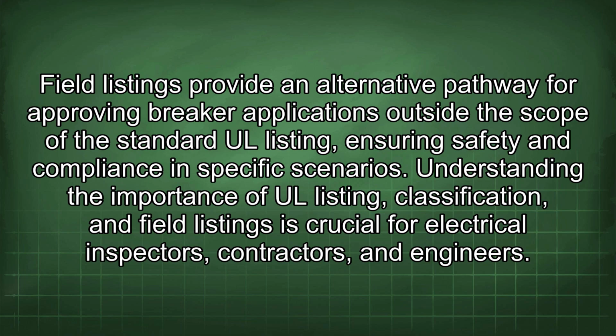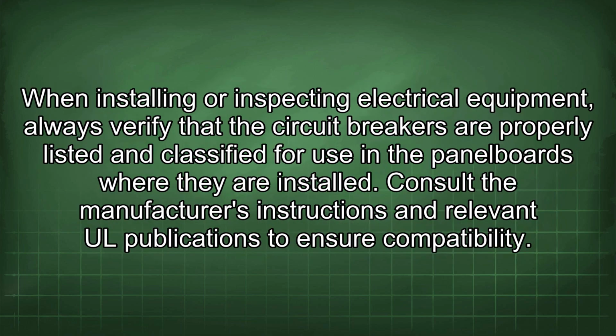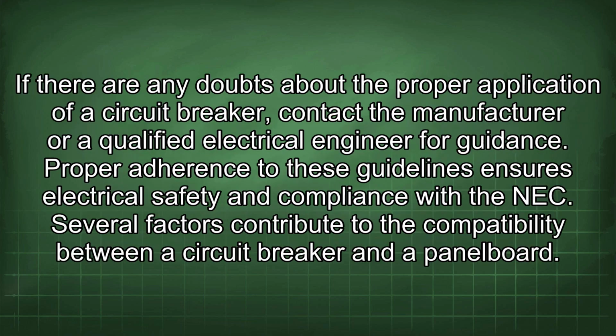Understanding the importance of UL listing, classification, and field listings is crucial for electrical inspectors, contractors, and engineers. When installing or inspecting electrical equipment, always verify that the circuit breakers are properly listed and classified for use in the panel boards where they are installed. Consult the manufacturer's instructions and relevant UL publications to ensure compatibility. If there are any doubts about the proper application of a circuit breaker, contact the manufacturer or a qualified electrical engineer for guidance. Proper adherence to these guidelines ensures electrical safety and compliance with the NEC.